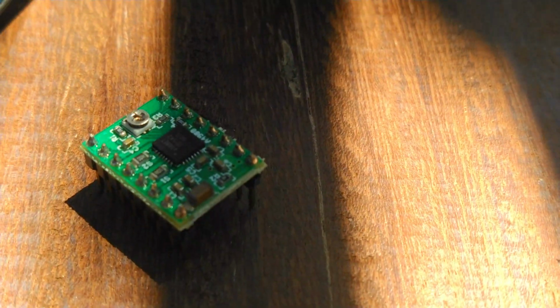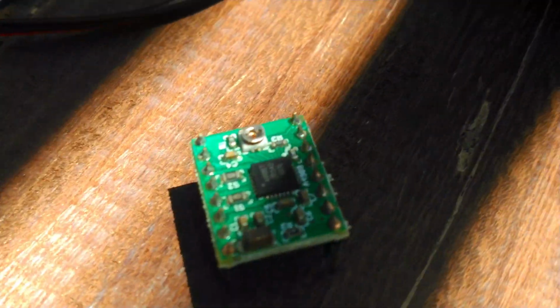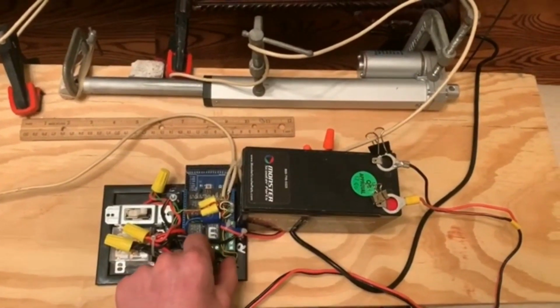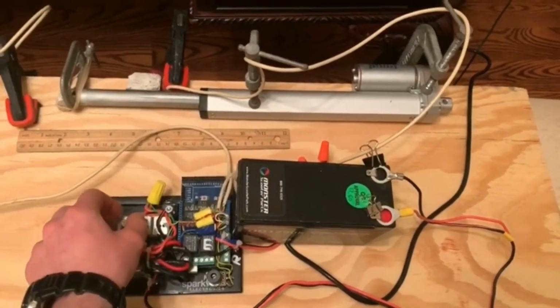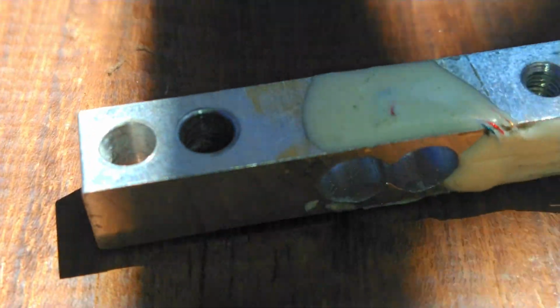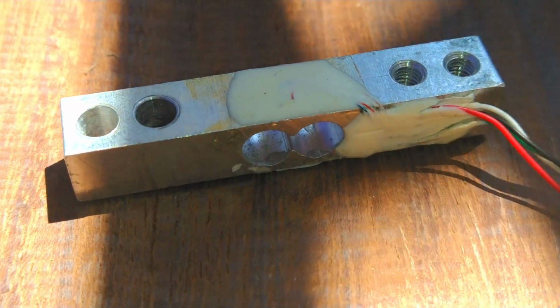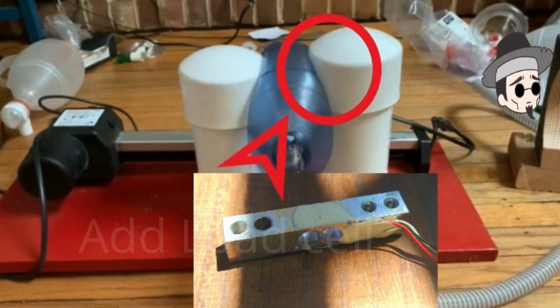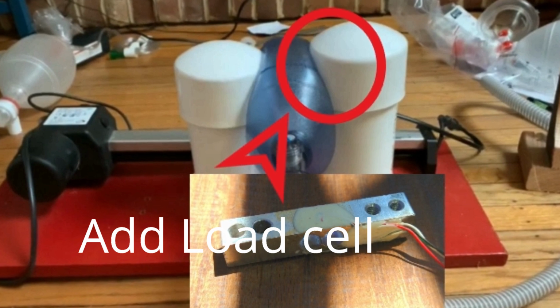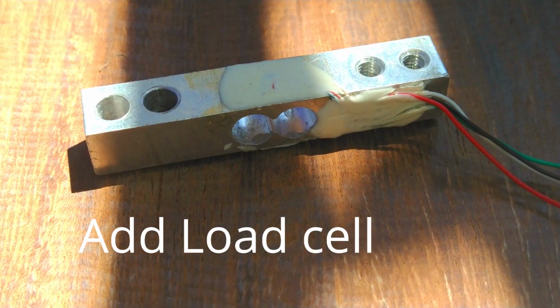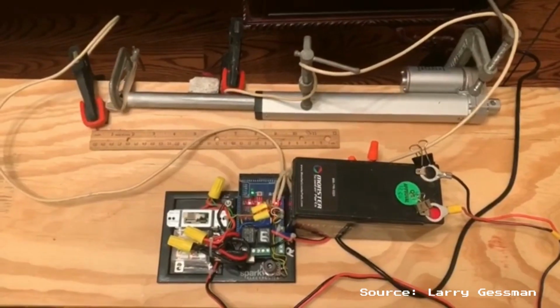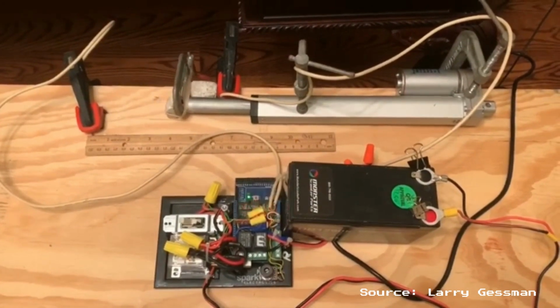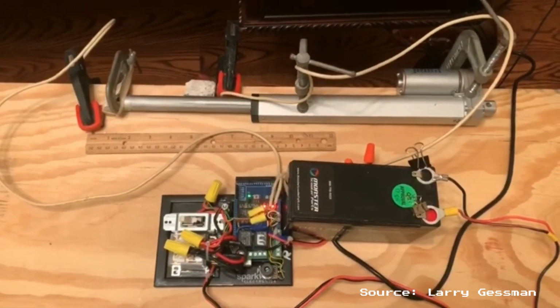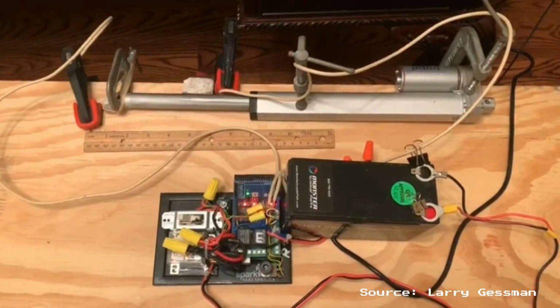Our idea is very simple. If we can control the speed of the linear actuator pressing the Ambu bag, we can control the volume or pressure on it. If we add a load cell to the pressure head, the load cell will measure the load on the Ambu bag. And here we can declare a variable which will be a function of the load on the Ambu bag. We can use that variable to control the RPM of the stepper motor.